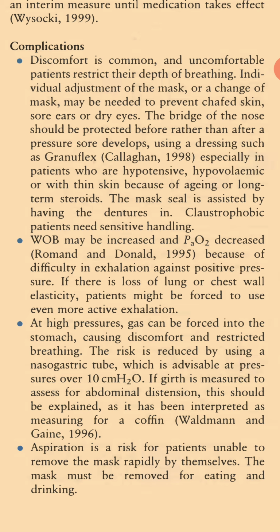Claustrophobic patients need sensitive handling. WOB may be increased and partial pressure of oxygen decreased because of difficulty in exhalation against positive pressure. If there is loss of lung or chest wall elasticity, patients might be forced to use even more active exhalation. At high pressures, gas can be forced into the stomach, causing discomfort and restricted breathing. The risk is reduced by using a nasogastric tube, which is advisable at pressures over 10 cm H2O.